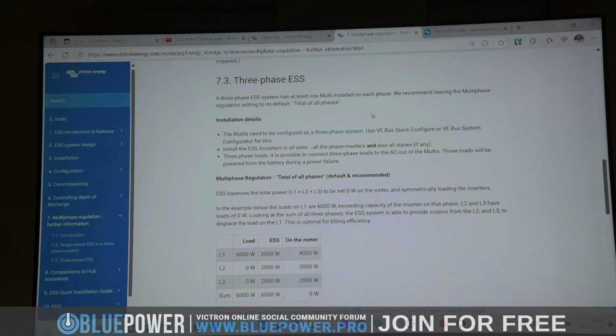Also, the energy meter that you use to measure matters. So like sometimes if you've got a 3-phase system, and you've got the old ET, the 340, it measures - even if you're allowed to export, it'll measure exporting 1 kilowatt out on your dashboard. It'll say your grid feed-in is this much, but you're actually importing 3 kilowatts at the time. So when the customer looks at it, they think they were exporting that much, but they didn't, because it doesn't work that way.